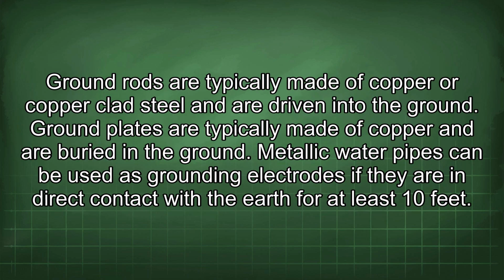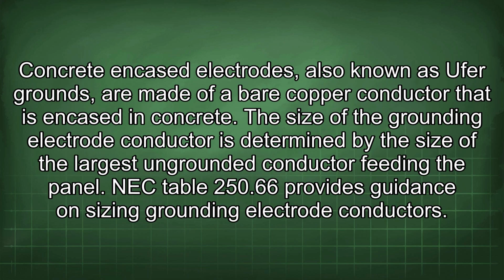Ground rods are typically made of copper or copper-clad steel and are driven into the ground. Ground plates are typically made of copper and are buried in the ground. Metallic water pipes can be used as grounding electrodes if they are in direct contact with the earth for at least 10 feet. Concrete encased electrodes, also known as UFER grounds, are made of a bare copper conductor that is encased in concrete.